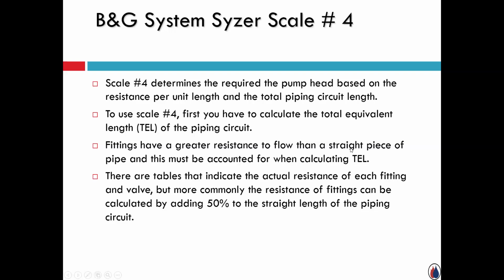All I'm saying here is whatever you figured on scale 2, because that was based on what? The pressure drop of a certain flow rate through a certain size pipe for 100 feet. Scale 4 says, how many feet do you have? 50? 5,000? What's your length of run? And it would do the calculation for you. To me, of the 5 scales, it's the most useless relative to how we operate today. But back in the day, it was part of the 5 scales. One other comment, real quickly.